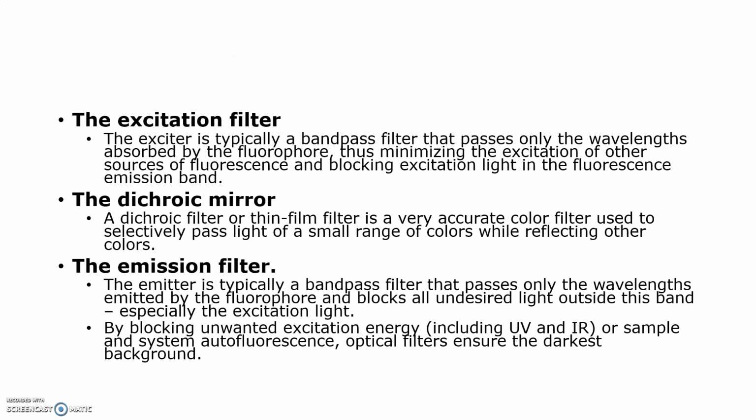Next is the excitation filter, another important part. The exciter is typically a band pass filter that passes only the wavelength absorbed by the fluorophore, thus minimizing the excitation of other sources of fluorescence and blocking the excitation light in the fluorescent emission band.